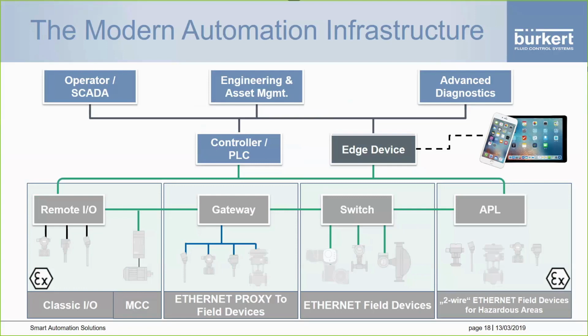Why not just do this in the PLC and SCADA like before? The problem is the amount of data involved. A smart modulating valve alone could generate up to 3 terabytes of diagnostic data in a year. Now consider you might have 100 valves on site - no PLC or SCADA system is going to want to process and manage that amount of data.